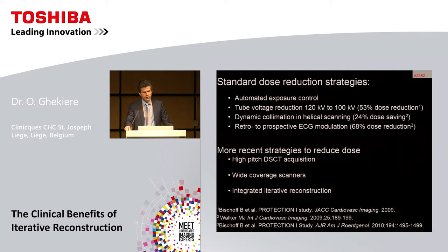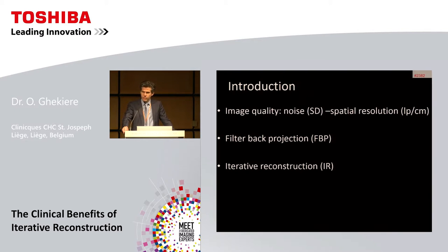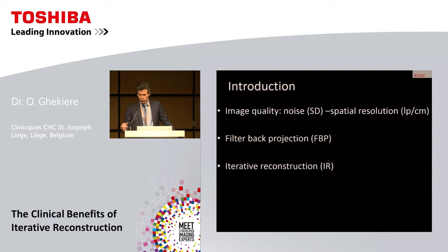More recent dose-saving strategies include high-pitch dual-source scanners, wide-coverage scanners such as the 320-slice scanner, and integrated iterative reconstruction. Image quality in CT is most often quantified as the amount of noise in the image, defined as a standard deviation, in relationship to spatial resolution defined as line pairs per centimeter. Compared to filter back projection, iterative reconstruction refers to an algorithm using mathematical and statistical modeling to reduce image noise by repeating iterative cycles.